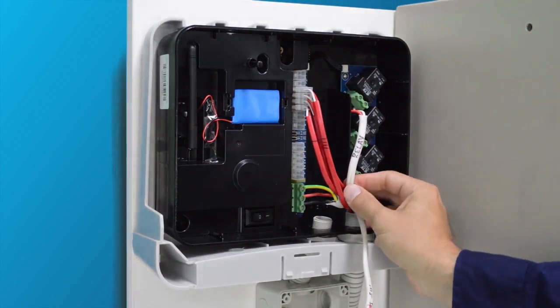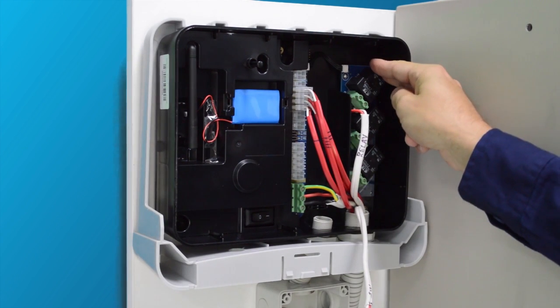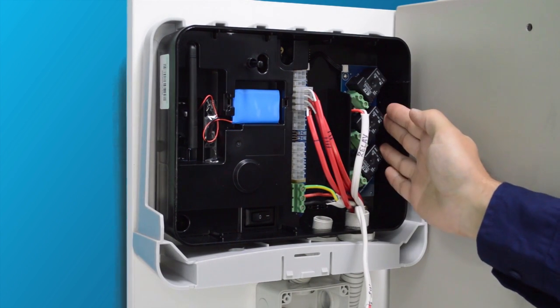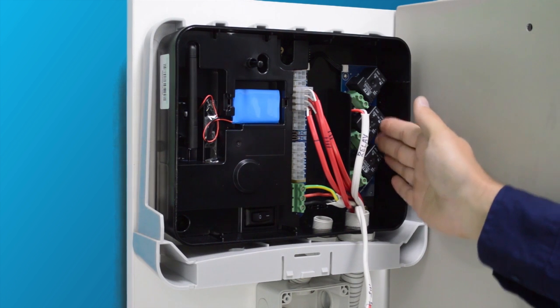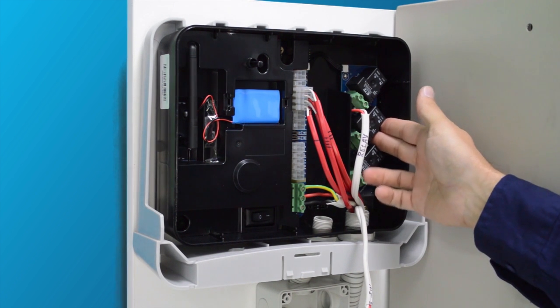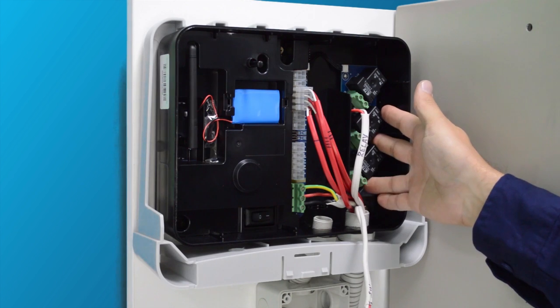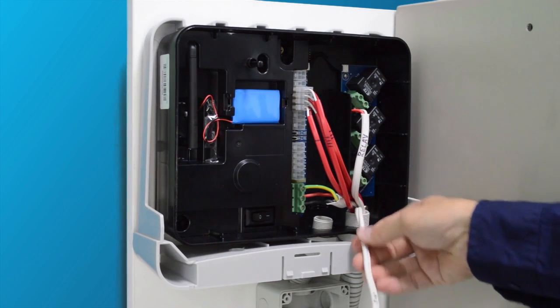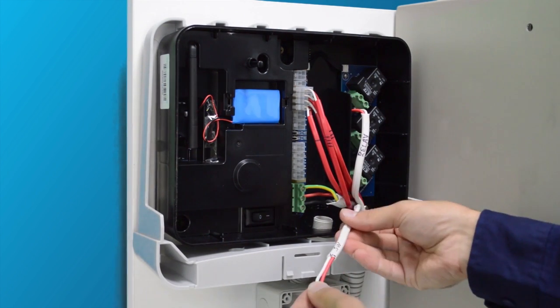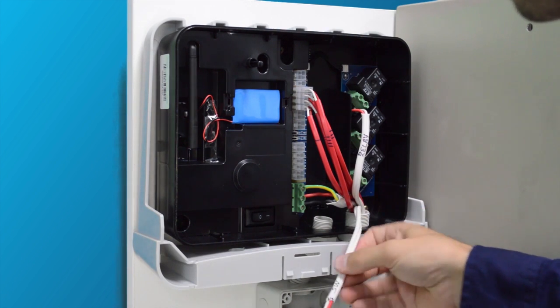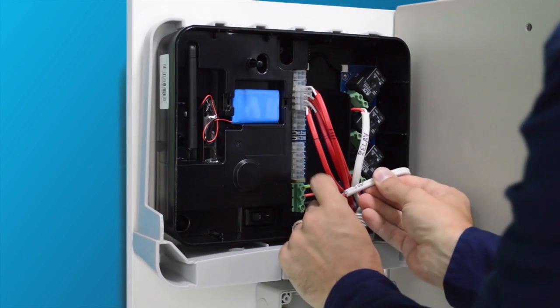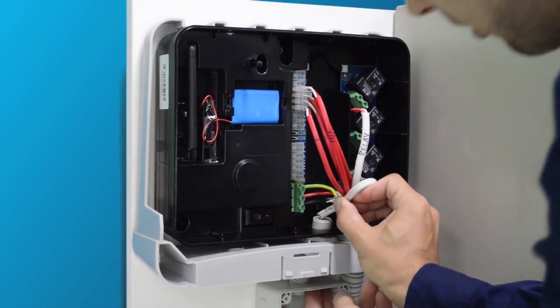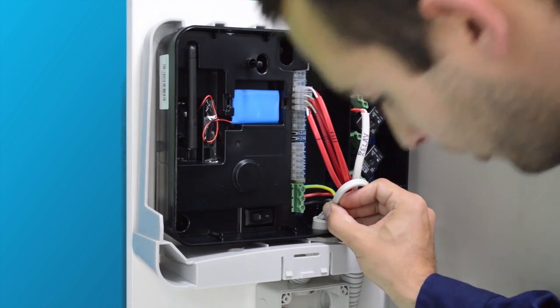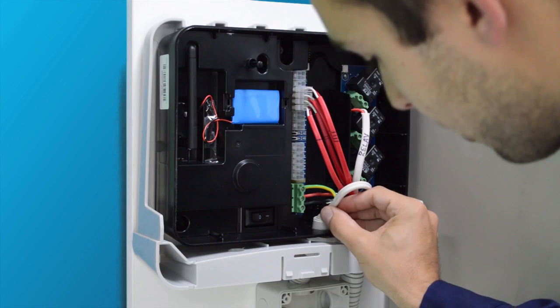For ease of demonstration, I've chosen relay 3 to connect into. It doesn't matter which relay you connect into, as long as you take note and set up the switching in the relevant relay online. To install a weatherproof bypass switch, take the second twin active labelled at both ends switch and run it into a weatherproof enclosure where we'll install our bypass switch.